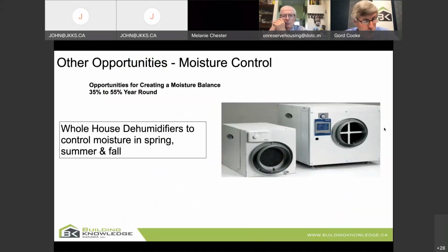For the coastal regions where you have very high moisture levels and not a lot of drying potential, in addition to ventilation and heating, you need dehumidification. A whole house dehumidification system can be ducted in with a furnace or with your HRV, to keep you under 55%. The key number here is if you don't have extended periods of time below 10 degrees Celsius, you need dehumidifiers. For those in remote northern communities where it's cold for long periods, you probably don't need dehumidifiers because you have really good drying potential - the colder the air is outside, the better the drying potential. But if you're living in relatively mild climates, coastal regions, dehumidifiers is where you'd like to get to.